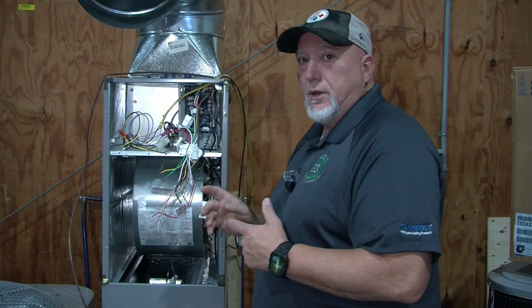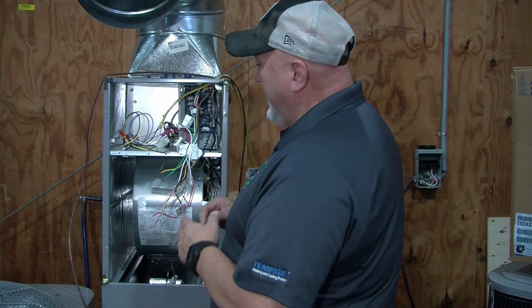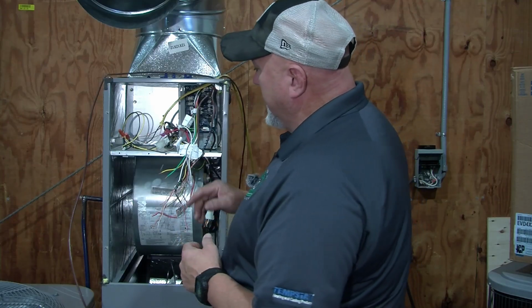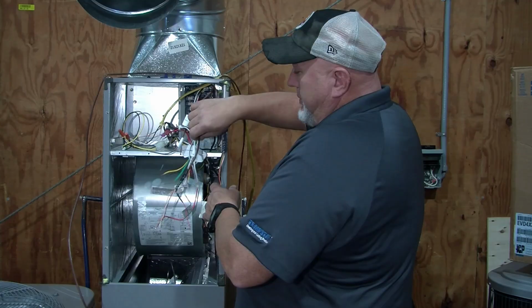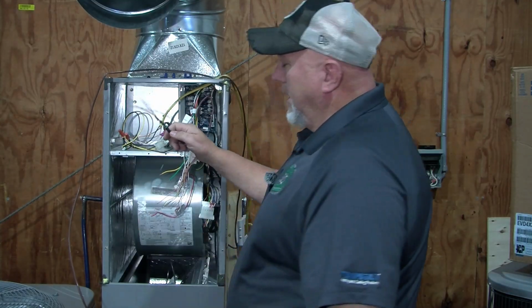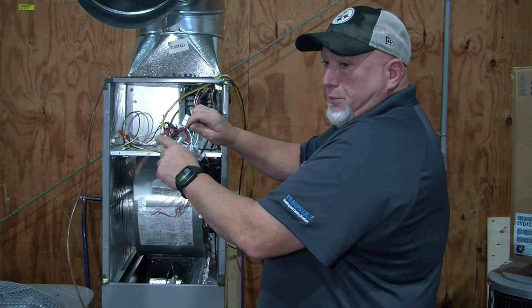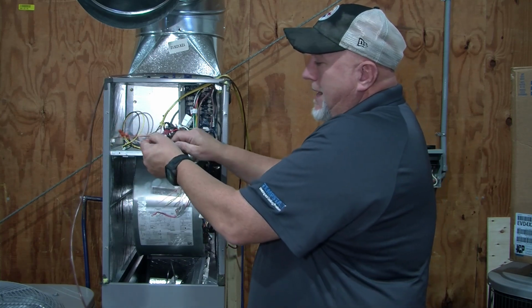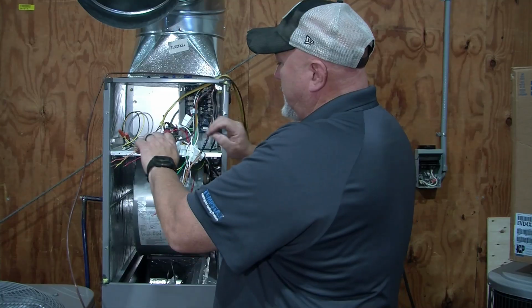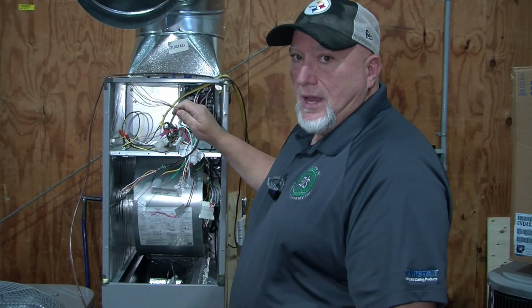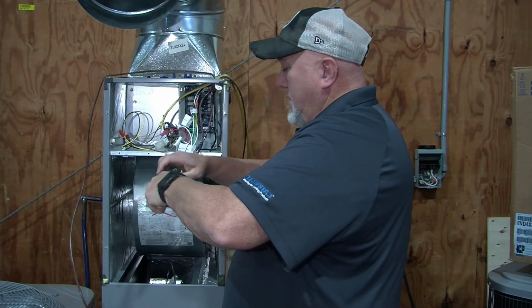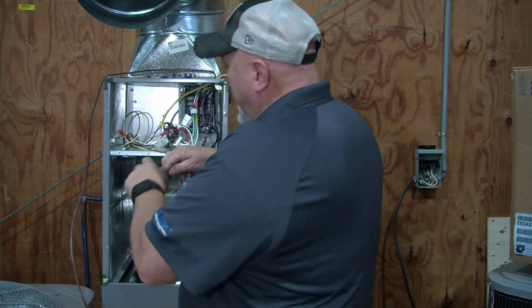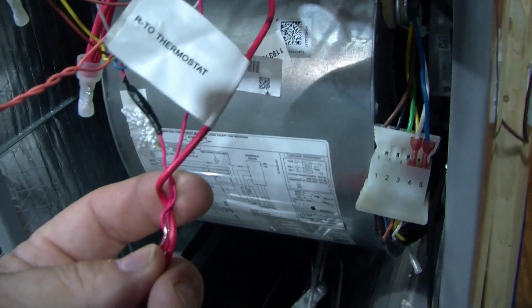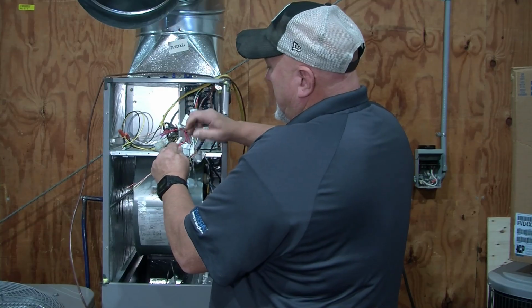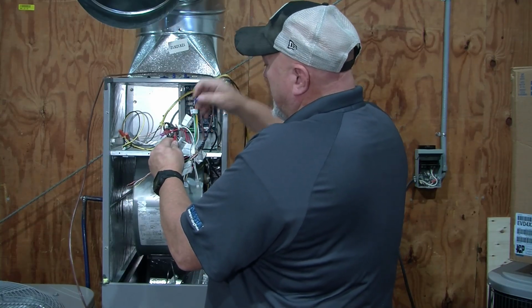So I'm going to get a closer up view of what we have here in just a second, and then we're going to go through this one wire at a time. What I've done is I've taken my wire from my condensing unit, and I just put some black electrical tape on it so you could actually see and know this is a condensing unit thermostat wire. This is the actual wire from the thermostat. Alright, so we got our red wire. Then you have your red wire here, red R to thermostat. So we're going to tie these together.